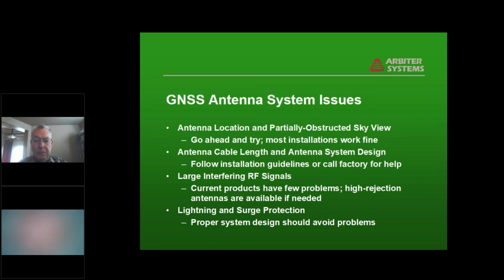Nowadays, we found that even with only GPS satellites, if you turn the thing on and let it run overnight, it'll generally find its position. And once it knows where it is, there's almost always at least one satellite visible. With multiple satellite systems, including Galileo and GLONASS, there's 3 times as many satellites, so the odds are that almost any installation these days will provide precise time without too much trouble. We've had people that have had questions over the years with antenna cable length and system design, especially if you have a long cable and you need to have preamplifiers in the line and all that. There's information provided to help people do that, in manufacturers' literature, and the factories are always willing to help you on that kind of stuff. Large interfering RF signals, typically that you'd find where the GPS receiver was co-located with RF and microwave equipment.